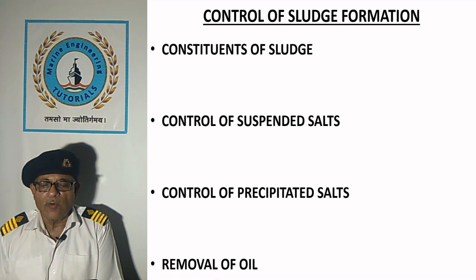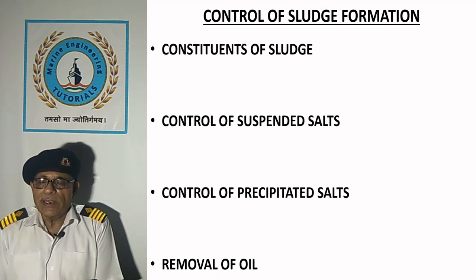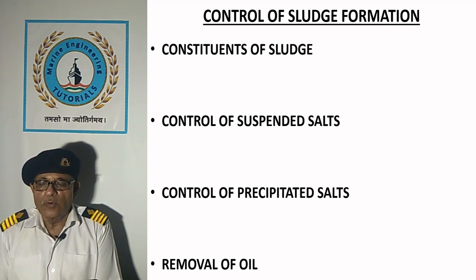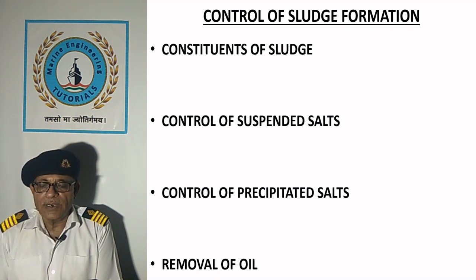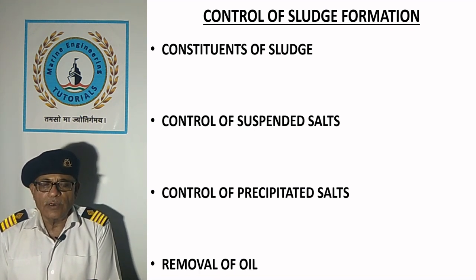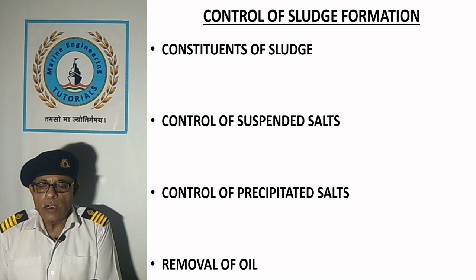Removal of oil: if oil gains entry into the boiler, liquid coagulant should be dosed immediately to prevent spread of oil on heat transfer surfaces. Coagulated oil should be removed from the scum blowdown valve until oil is completely removed. Coagulants keep the oil and precipitates in colloidal suspension until they are blown down. When the boiler drum is opened for inspection or survey, thorough cleaning should be carried out with a high-pressure jet using distilled water to remove any foreign matter adhering to the boiler surface.